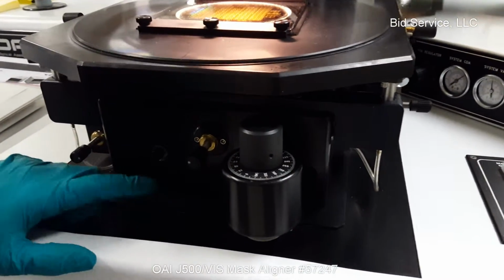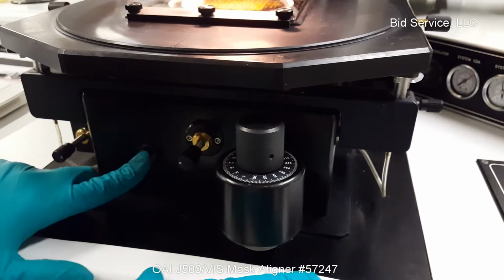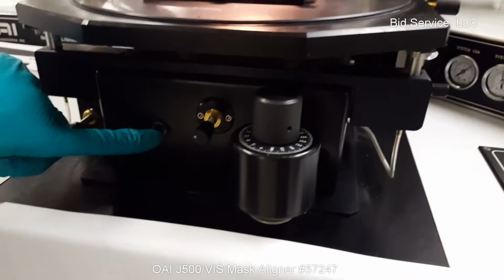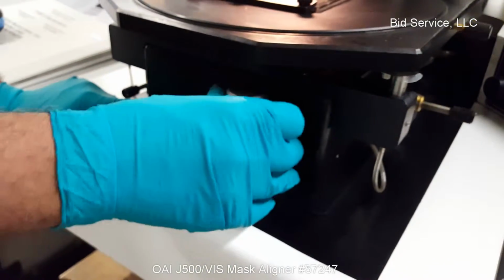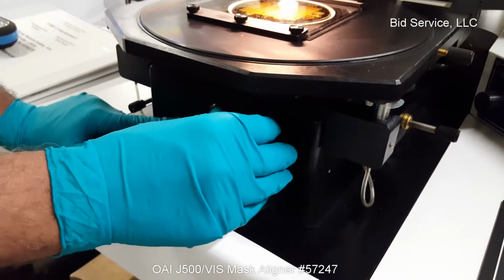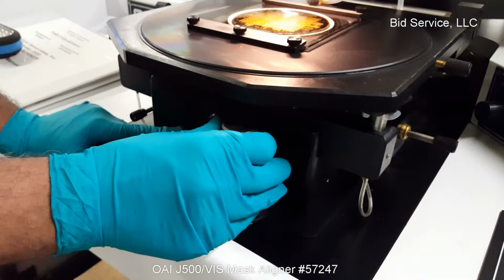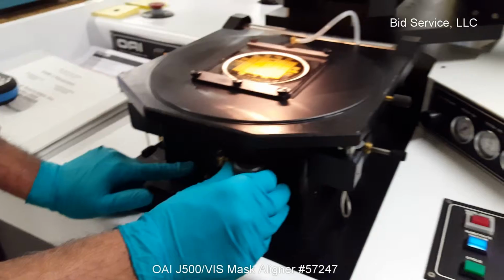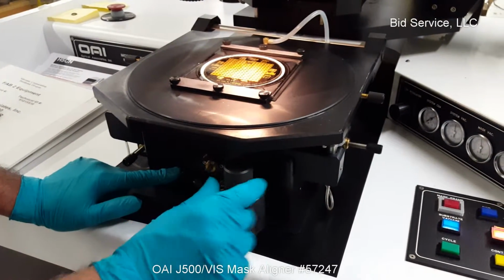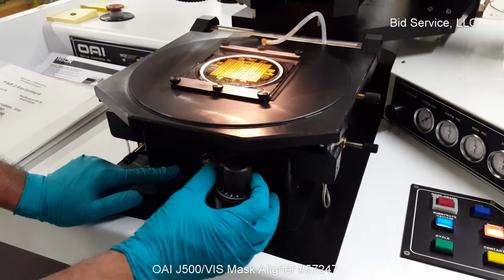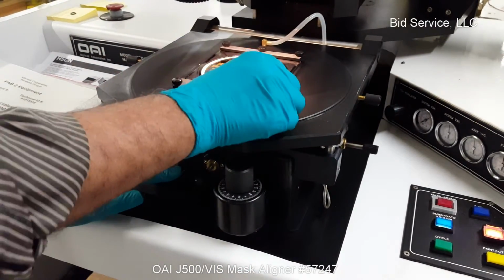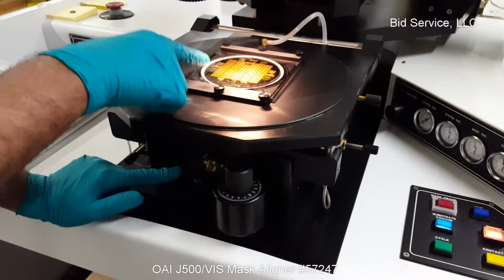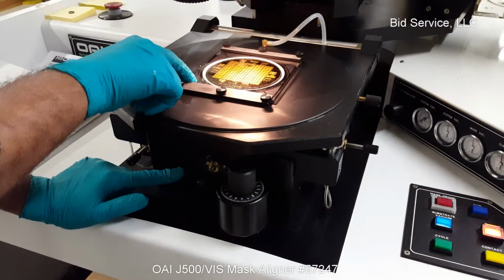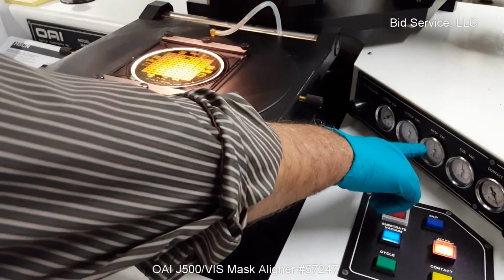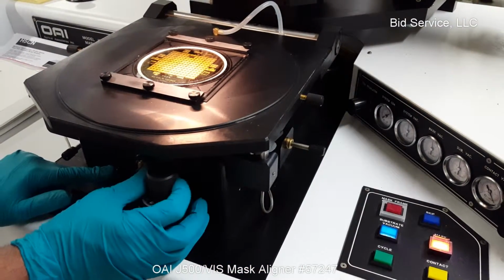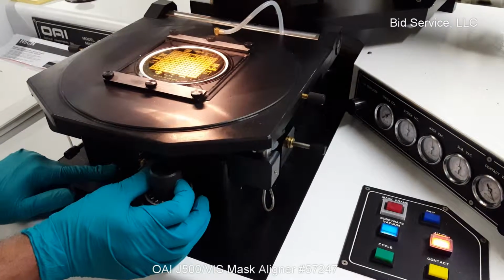So for all same thickness wafers, first press the ball lock push button, which is over here, and rotate the knob till the substrate comes in contact with the mask. Excess rotation of the z-axis knob will dislodge the mask. The mask will be lifted off its vacuum chuck holder, and the mask vacuum will start to drop a lot.